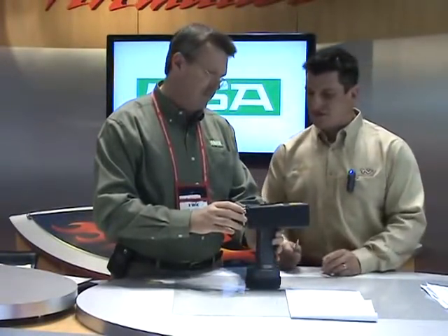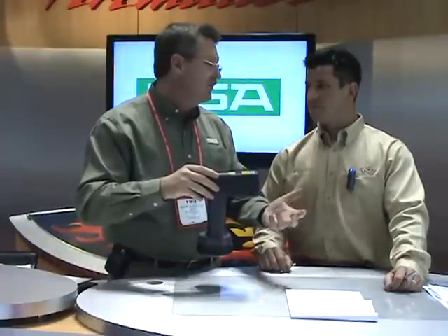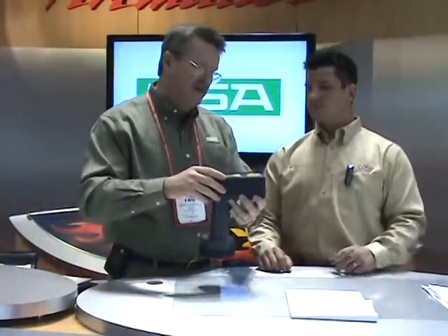The only other thing I'm noticing is you've got one single HAZMAT-CAD unit. Are there other HAZMAT-CAD units from MSA? We've got the HAZMAT-CAD and this — the HAZMAT-CAD Plus. This bottom portion contains toxic sensors, so you can detect certain toxic industrial chemicals — things like chlorine or hydrogen — which could be used in terrorist applications, such as pesticides they might obtain relatively easily. The top portion is your chemical warfare agent detector. Customers don't have to get the Plus; you can purchase just the chemical warfare agent detecting portion. So there are packages with the HAZMAT-CAD that you can configure and get from MSA and Firematic.